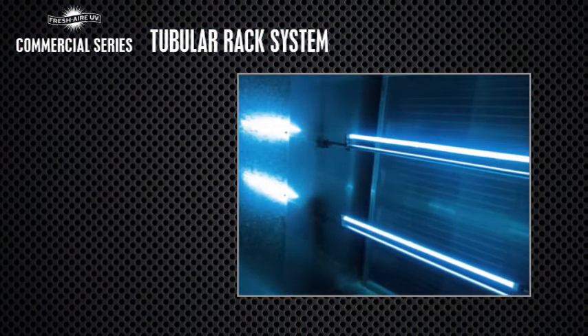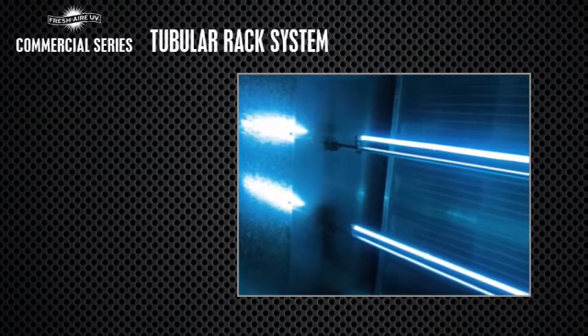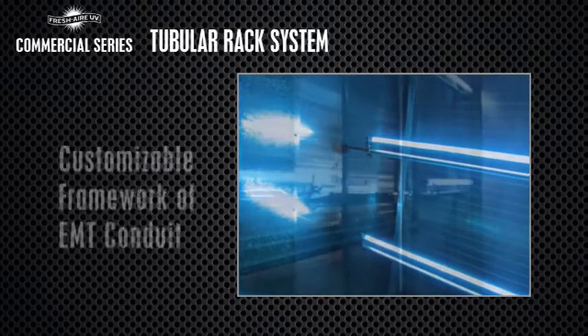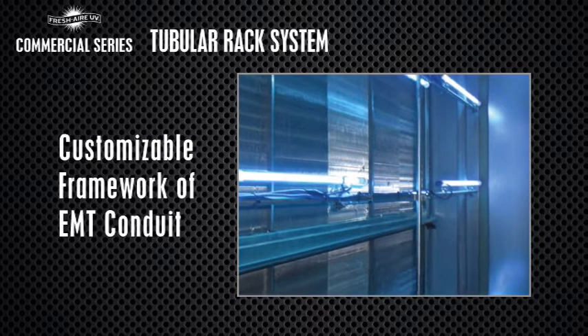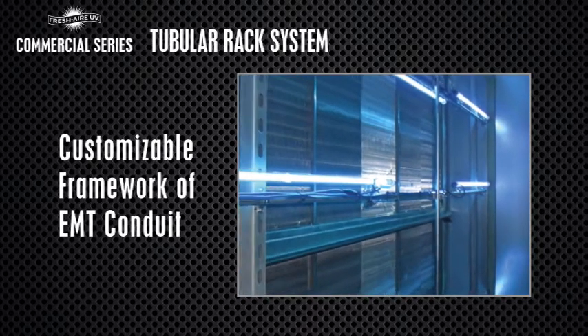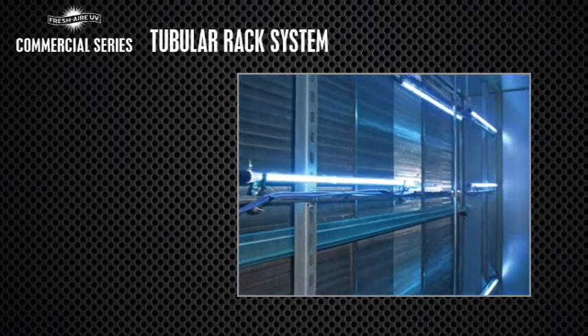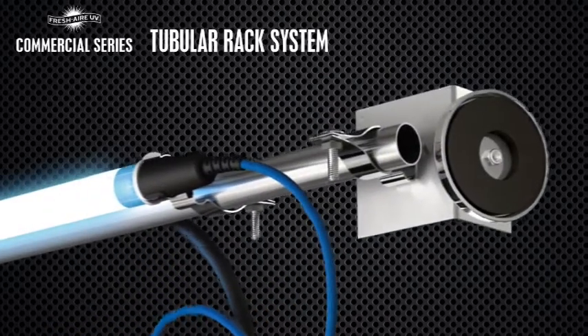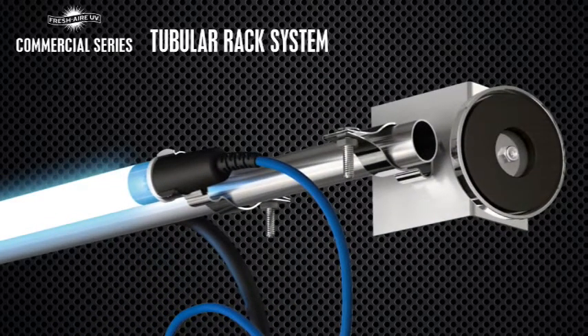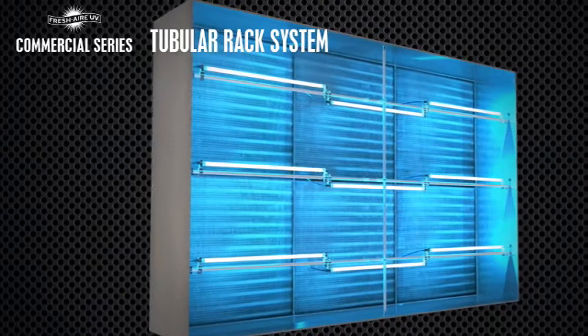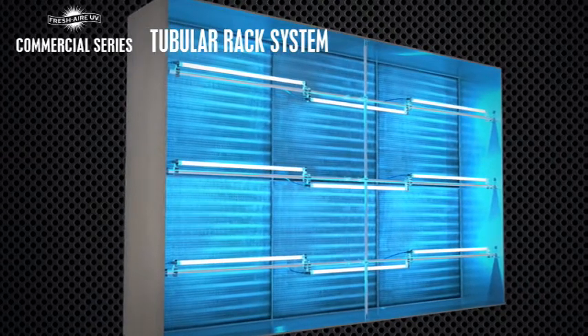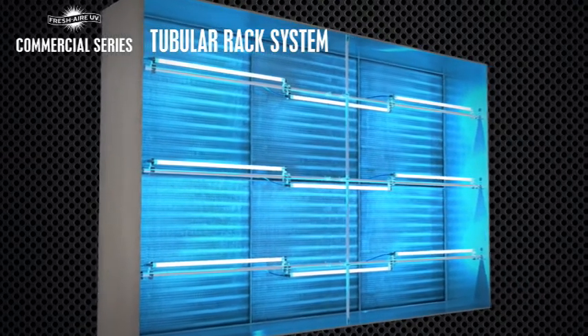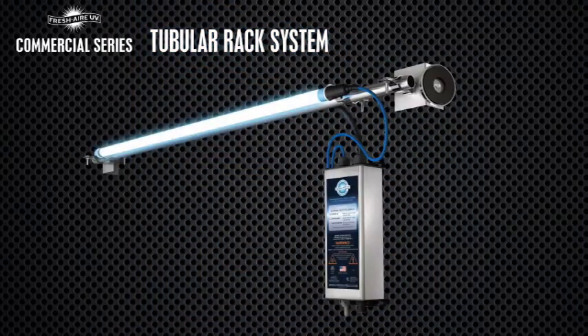Our most popular commercial product is the tubular rack system. It's designed around a customizable framework of off-the-shelf EMT conduit which serves as a support for the UV lights. The framework design, including optional mounting magnets and vertical supports, allows for multi-lamp installations, customized to fit virtually any HVAC application. It uses the same lamps and power supply as the standard system and comes with all the hardware necessary for assembling the rack except the tubing.